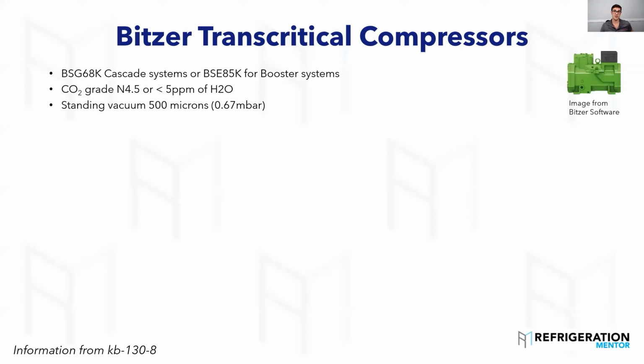They want oil changes done in their racks because they're seeing there's a lot of moisture in the system, and that causes major issues, especially with CO2, because it can freeze up valves very easily and plug things up. So you need to understand what the manufacturers recommend. And I know I've been on many job sites. I've worked a lot, and there are tight timelines. Jared, I'm sure you've been involved in doing construction.